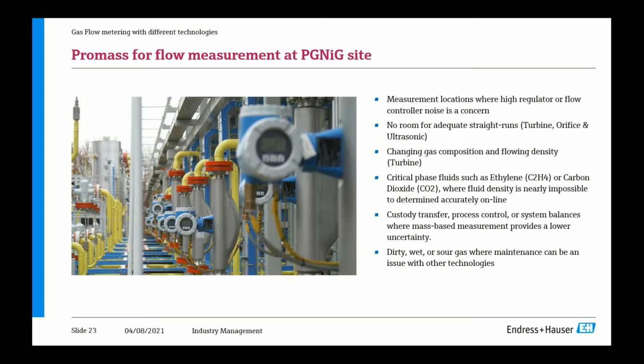We know that the time difference between the inlet and outlet of the tube is proportional to the mass flow of the gas. This is true, of course, for compressible and non-compressible fluids. Therefore, a Coriolis meter can measure mass flow rate for a gas application without needing to compensate for changes in density coming from pressure and temperature changes. Unlike other technologies, the Coriolis meter can measure the mass of gas even if the composition is changing. Another advantage in the installation is that Coriolis meters are multi-parameter: you not only get mass flow, but you also get temperature, viscosity, and density as well.